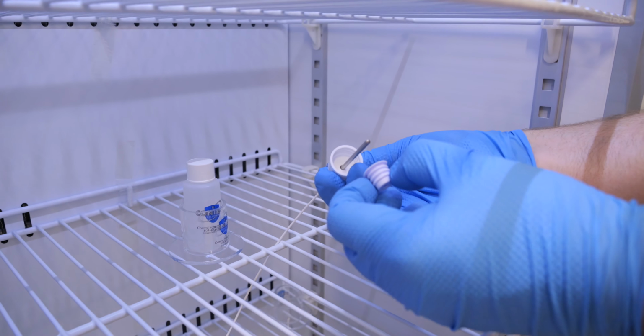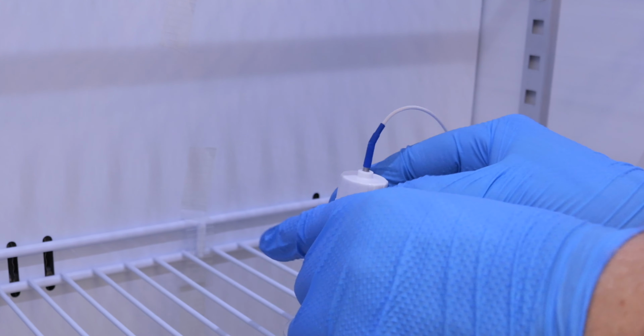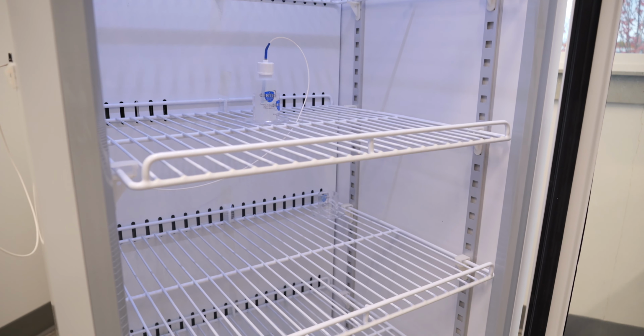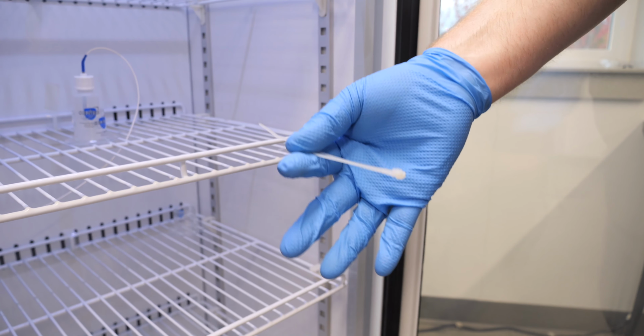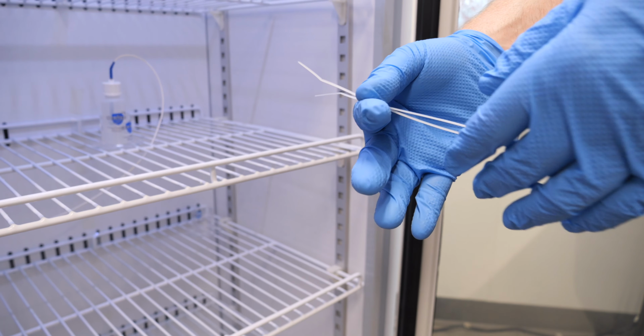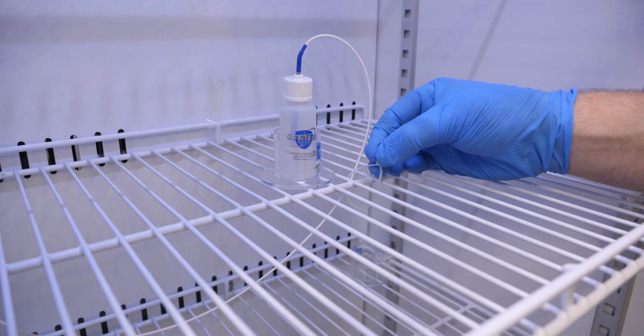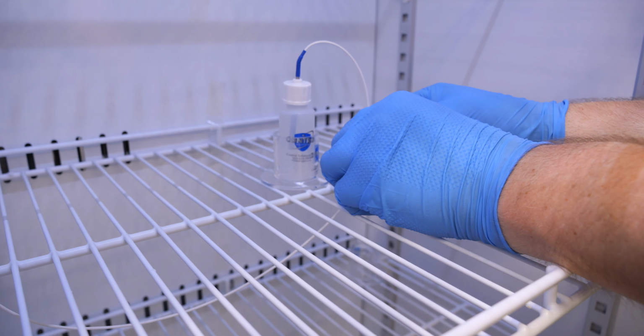Now we reinsert our bottle cap first, and then we install our probe seal next. And then once installed, it will look just like that. The seal will be underneath the lid. And now we simply remove our solid cap, and we'll insert the whole probe assembly into the bottle like so. Once we have our probe buffer bottle assembled, we want to attach the probe cable to our racking. We include extra zip ties so we can hold the cable down to the crossbar of our rack.